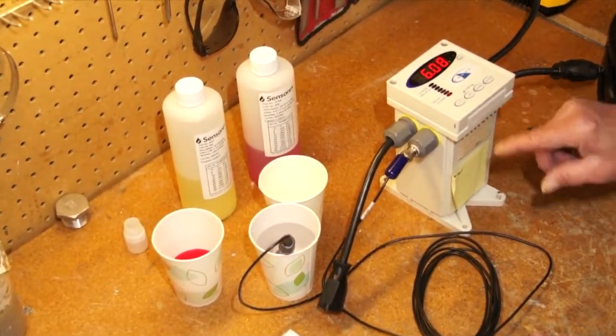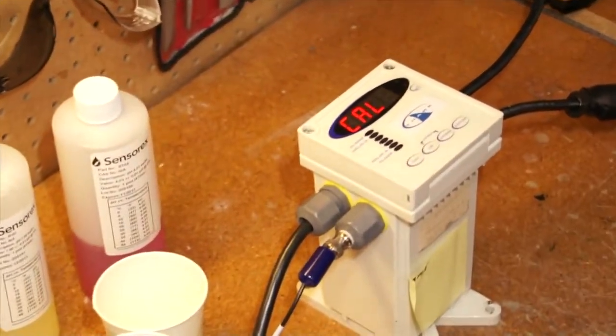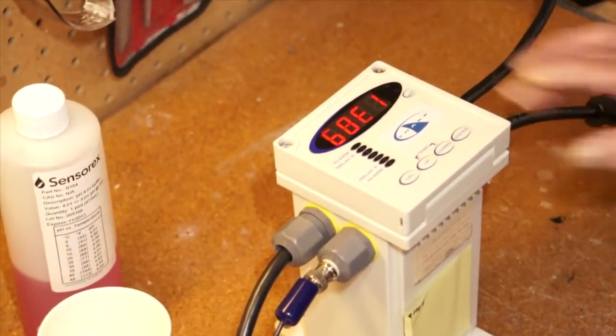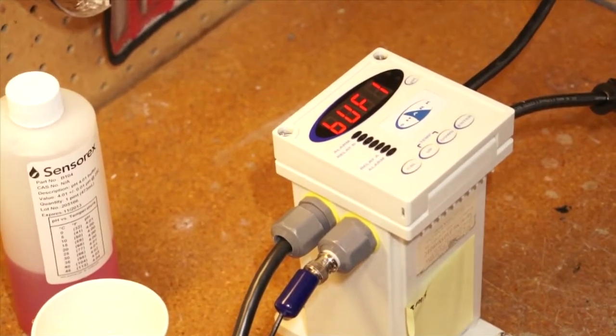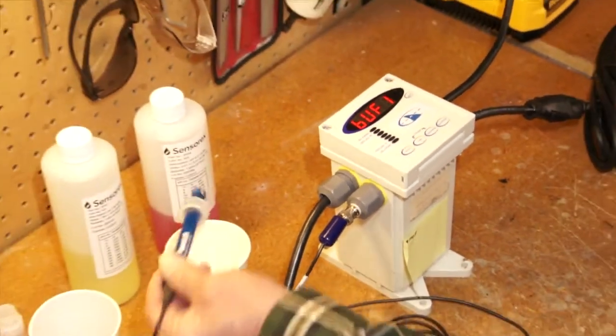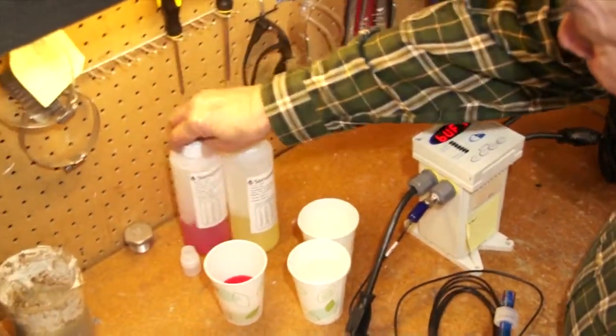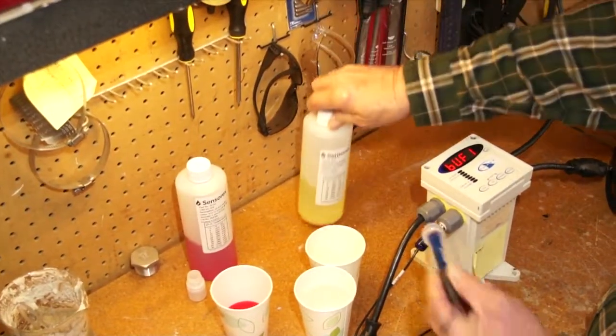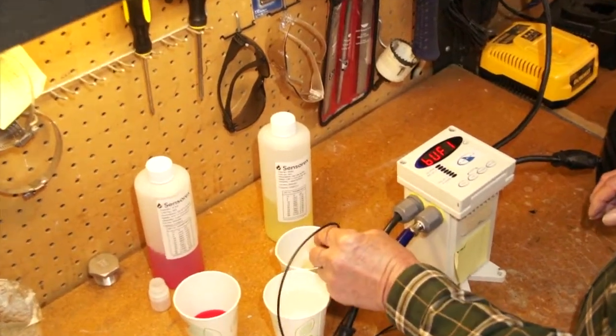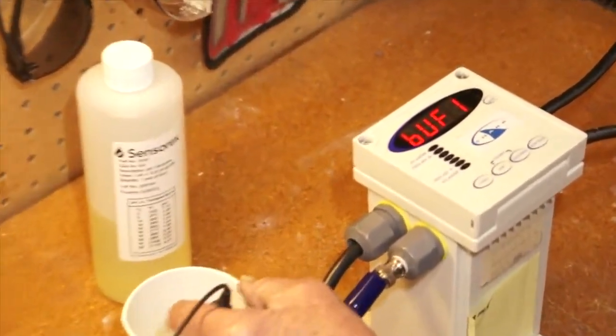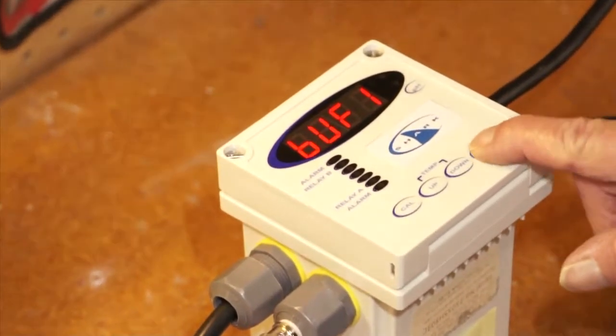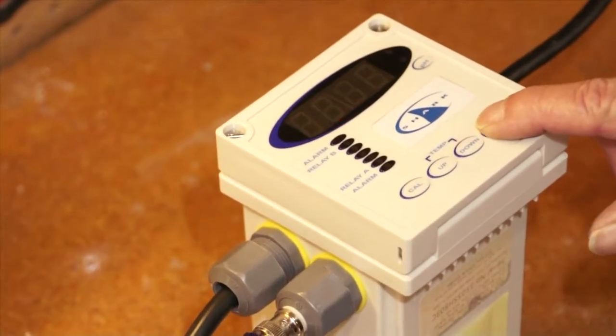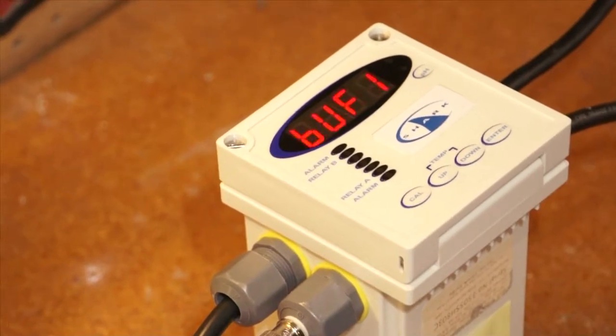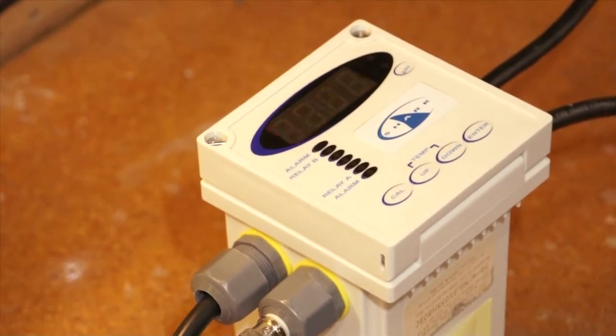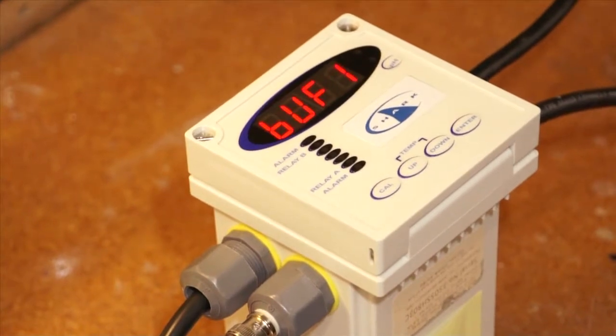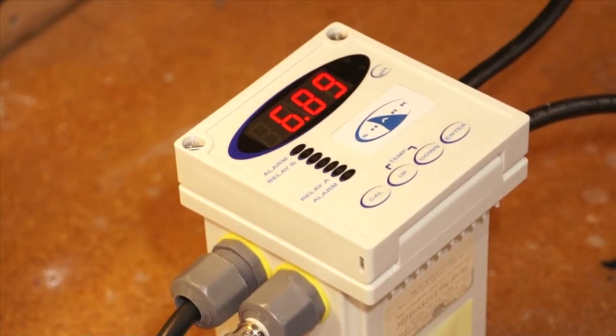For everyday calibration, the operator simply presses the cal button, calibration, and then hits enter. And once the probe is rinsed in distilled water, placed in buffer 1, which is the yellow pH 7 material, and the order is very important. You always test the pH 7 first. You place your probe in that solution, hit enter again, and then you wait a moment to see what pH reading we're going to have on the controller to see how much we have to adjust it.